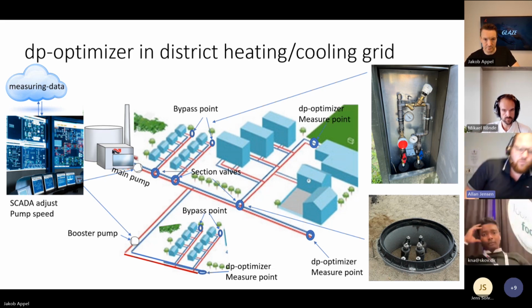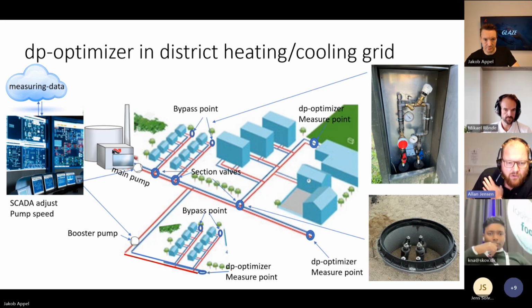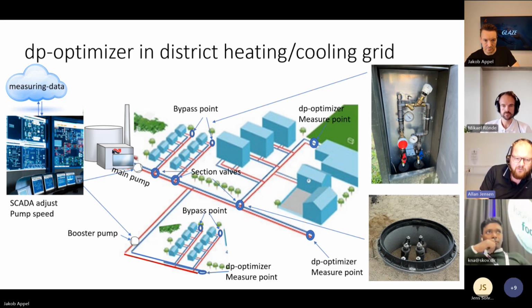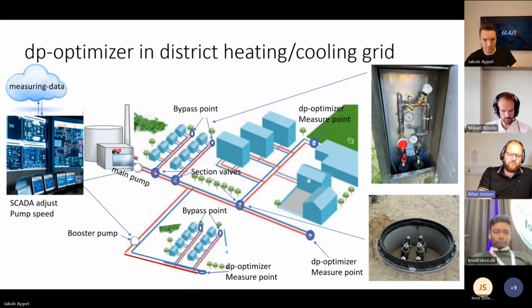We have in the grid we are measuring pressure. If we look here in the section valves, which are valves on the main grid that divide it into sections, we are measuring temperature and pressure in there. And when we do that, we have the possibility to control the main pumps and lower the pressure to just the accurate pressure, so we don't have more pressure than is needed. And by that, there is a lot of savings. We can find up to 20% savings by year to have the accurate pressure.